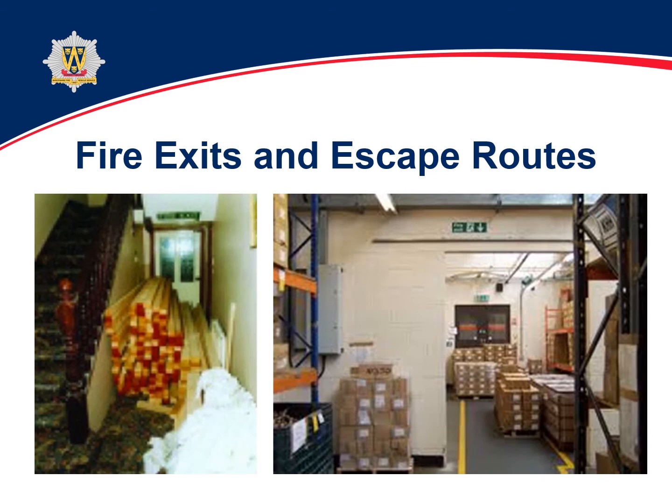Now fire exits and escape routes then. When we look at escape routes and fire exits, this is an escape route that leads to that final exit. And in the pictures you can see that these routes are blocked by stock. So once you've designated these routes, make sure that they remain clear and unobstructed so they are available to use at all material times. Now when you carry out your checks of these escape routes, when you reach that fire exit, that final door, before you get to outside to a place of safety, always make sure that you open that fire exit door and make sure that it's clear on the other side.